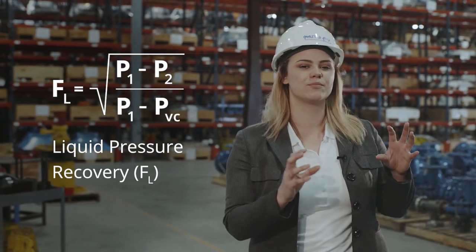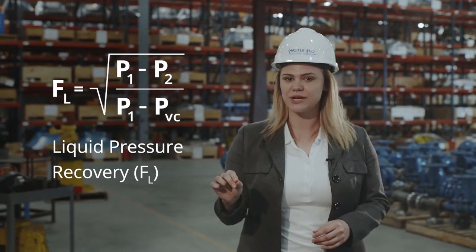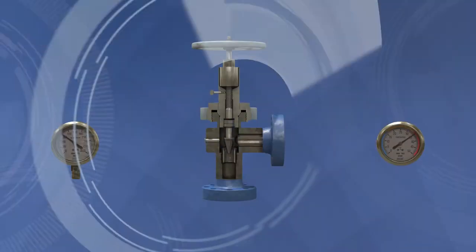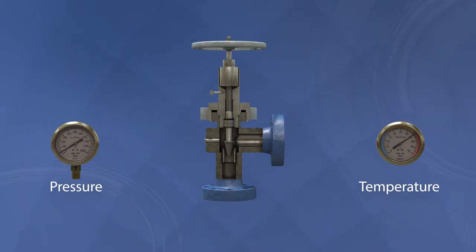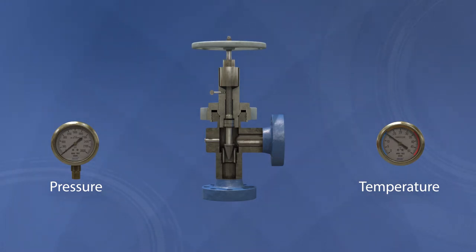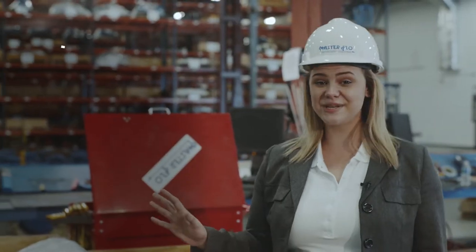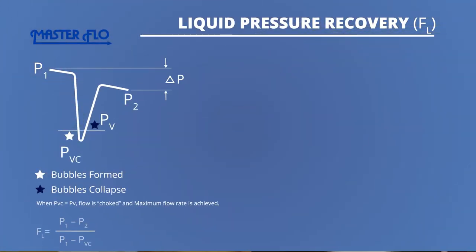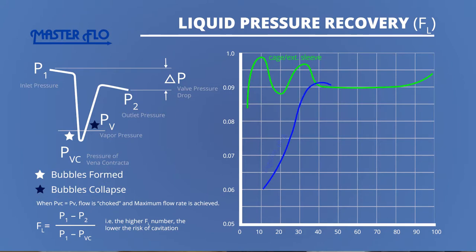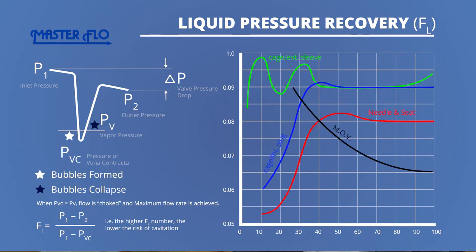Liquid pressure recovery is the ratio between the pressure drop and the difference between the upstream and the vena contracta pressures. If the pressure in the choke falls below the vapor pressure of the liquid, cavitation may occur, greatly reducing the pressure in the valve. The susceptibility to cavitation is governed by the valve FL number, which determines how low the pressure can get inside the valve. In extreme cases, freezing of gas may occur due to hydrate formation. As you can see, the cage with external sleeve design provides a higher FL over a wider range of valve openings. The higher FL number means a lower chance of cavitation and consequently, a lower risk of damage.